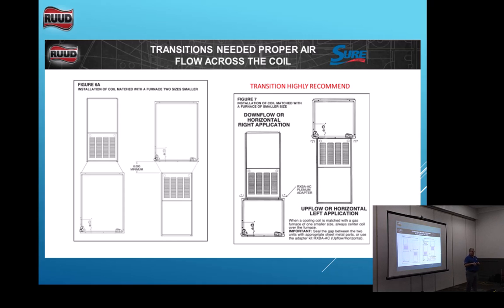Okay? It creates turbulence. If we have turbulent air going across that evaporator coil, we're not getting clean linear air going across it in good contact with that furnace and for that evaporator coil. So does it hurt to take them out? Well, they're in there for a reason. I haven't seen any problems with them, but they made it for a reason. And if you have warping pans and stuff, you have airflow issues further down the line, is what I would say. But this is what Rheem has come out and said, and their installation instructions don't say anything about being able to take it out. So to not come across any problems, I'll always tell you, follow the installation instructions, okay?